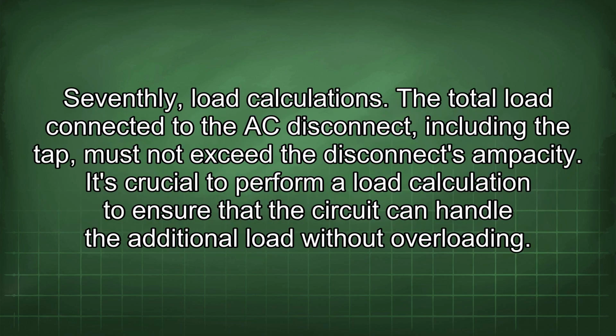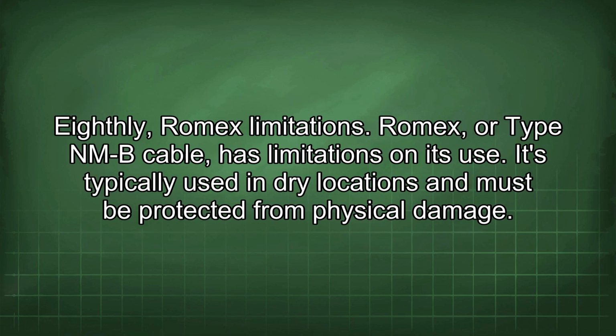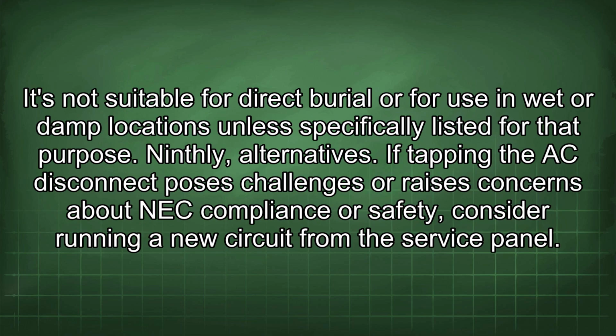Seventhly, load calculations. The total load connected to the AC disconnect, including the tap, must not exceed the disconnect's ampacity. It's crucial to perform a load calculation to ensure that the circuit can handle the additional load without overloading. Eighthly, Romex limitations. Romex, or Type NM-B cable, has limitations on its use. It is typically used in dry locations and must be protected from physical damage. It's not suitable for direct burial or for use in wet or damp locations unless specifically listed for that purpose.